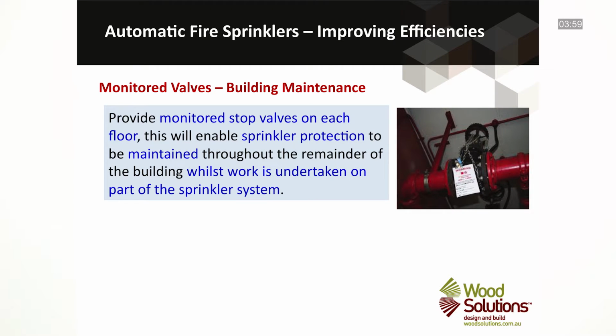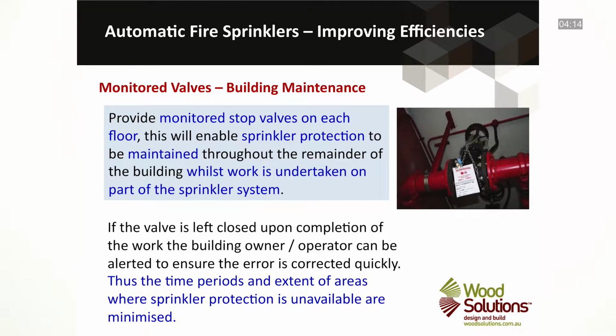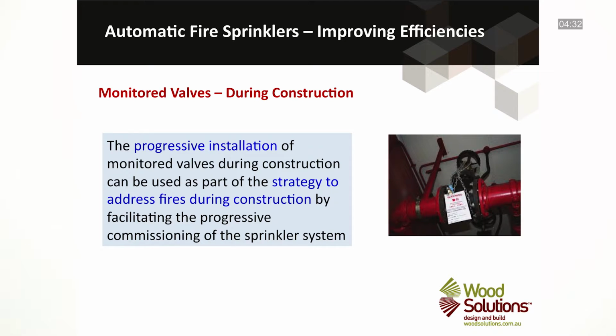It is also recommended that monitored stop valves be provided on each floor, though this isn't a requirement of the standard. This will allow isolation of building areas and enable sprinkler protection to be maintained throughout the remainder of the building, if work needs to be undertaken on part of the sprinkler system or on a certain building level. If the valve is left closed upon completion of the work, the building owner can be alerted to ensure the error is quickly corrected. Thus, the time periods and extent of areas where sprinkler protection is unavailable are minimised. This is a feature that should certainly be discussed with the building developers and owners. The progressive installation of monitored valves during construction can also be used as part of the strategy to address fires during construction by facilitating the progressive commissioning of the sprinkler system.